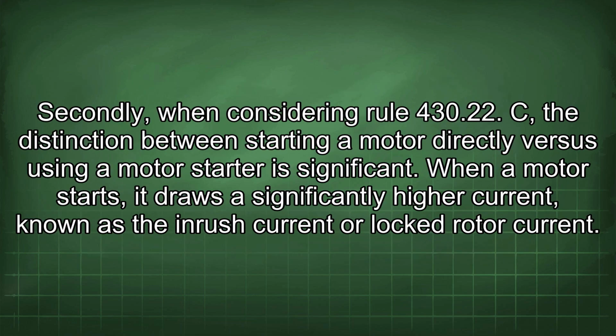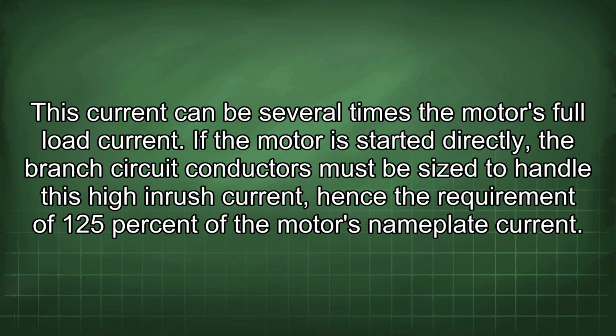Secondly, when considering Rule 430.22, the distinction between starting a motor directly versus using a motor starter is significant. When a motor starts, it draws a significantly higher current, known as the inrush current or locked rotor current. This current can be several times the motor's full load current. If the motor is started directly, the branch circuit conductors must be sized to handle this high inrush current, hence the requirement of 125% of the motor's nameplate current.